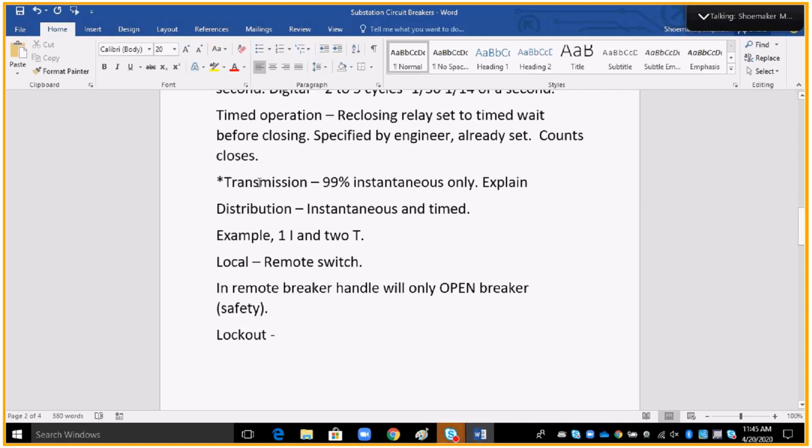I want to have it instantaneously open because really, in that line section, I have not lost any substations. There's nothing in between. My loop, transmission, stays looped all the time, and my loop is still able to keep all the other stations with power. If I have an outbound breaker on station 1 and an inbound on station 2, both of those breakers will open. It's actually, if you want to say it, line isolation automatically.